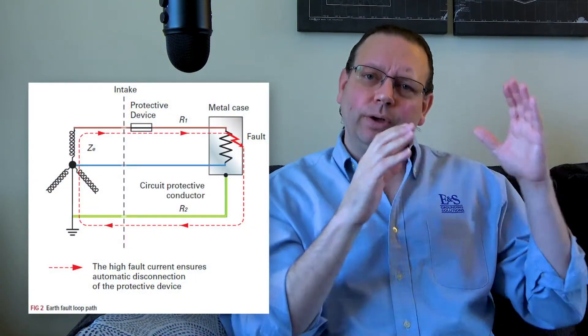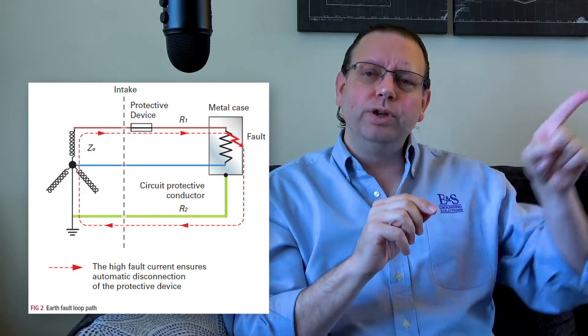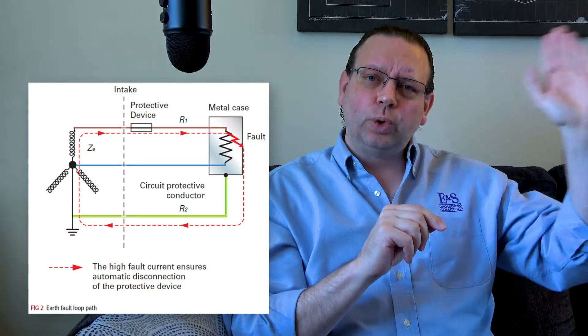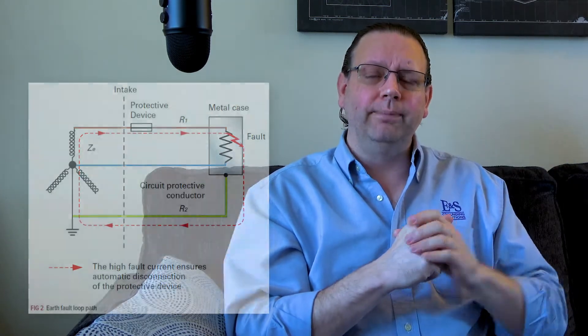What happens is that current comes in and the hot wire is accidentally tied, in this case to the ground wire with no resistance. So a max current flows through, goes down our ground wire back to our circuit breaker box, through the neutral ground bond in the box, up the neutral wire to the transformer that's owned by the utility company hanging out on the pole. Hits the center tap of the winding, goes across the winding, causing a massive current to flow.